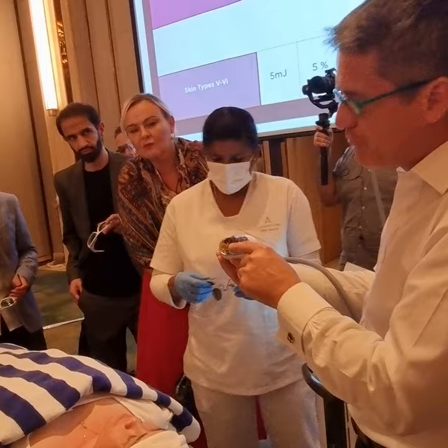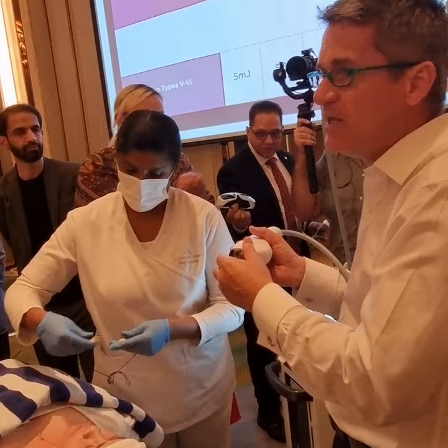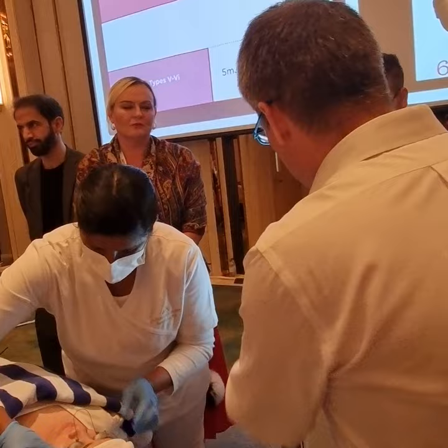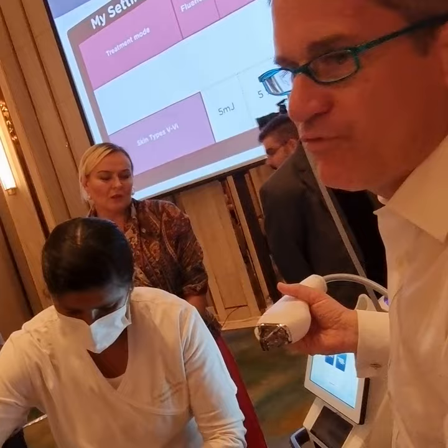So to get the FDA approval, they had to make the tip a disposable that is not going to be used in 2 different patients. That's why it has a time counter. After 30 minutes, you have to throw it away. They know you need about 7 minutes to do a face treatment, so they give you 30.